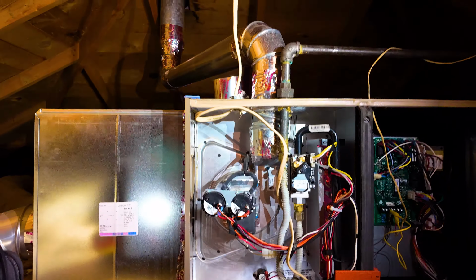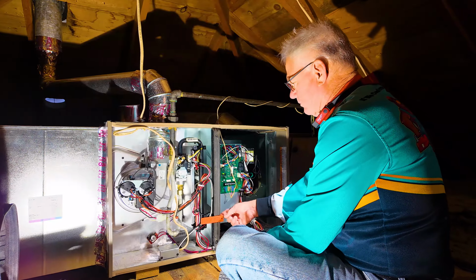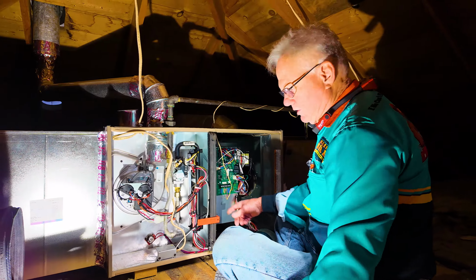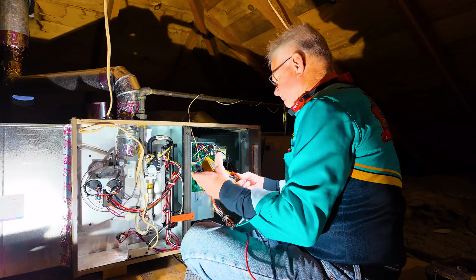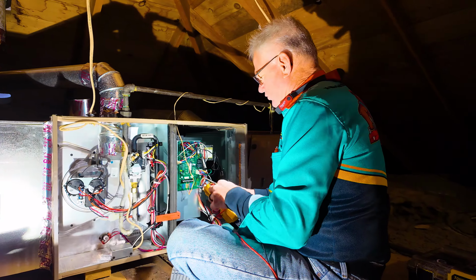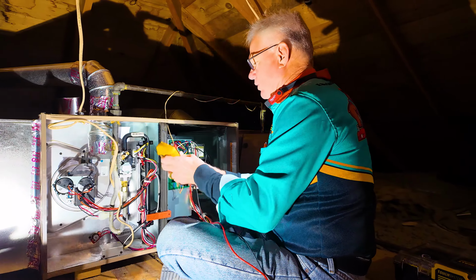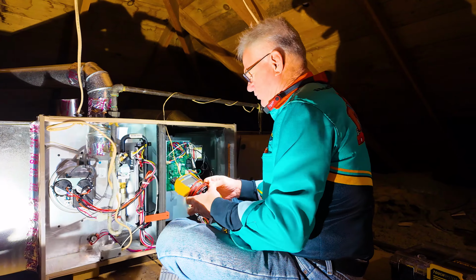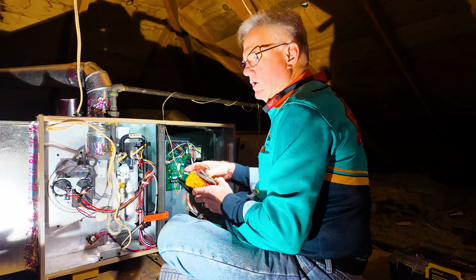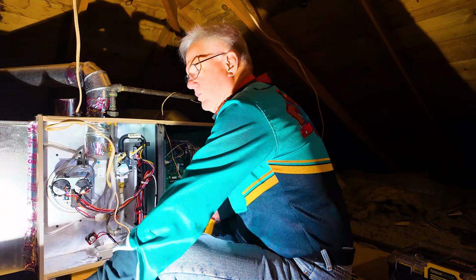All right, so that's it. Now we're going to go ahead and wrap it up because I think we're good to go. I'm going to take the call for heat off with my jumpers here. So now the thermostat's off. The flame went off. I'm going to leave the blower going for a minute before I take off the safety switch on the door, because I want the blower motor to keep going so it doesn't overheat the heat exchanger. It says it fired up. So that'll go, and it'll cut off here in a second when it cools down. I'll just be putting my tools away here in the meantime, and we'll call that a wrap.